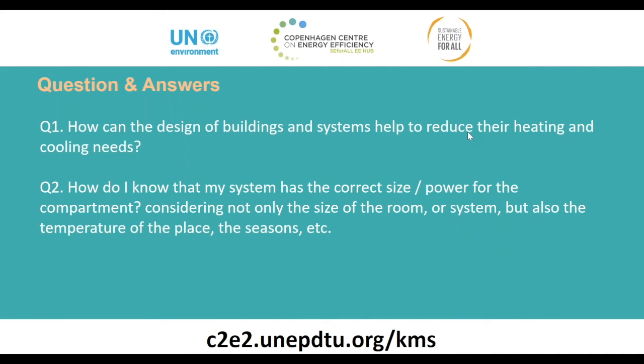Technical data, the R values or U values of the windows, walls, roofs, glazing details. You should also be having an idea of efficiencies of the cooling or the heating system that you intend to procure, if you are talking about design. Then based on all these parameters, you can theoretically calculate and see what your heating or cooling requirements are, and then compare with the existing systems. Is it something what you have calculated? Is it matching, or are over capacities available, or are these systems actually under design based on your theoretical loads?